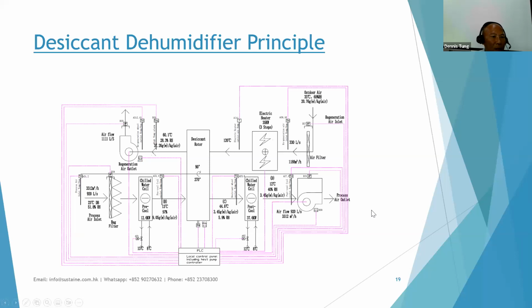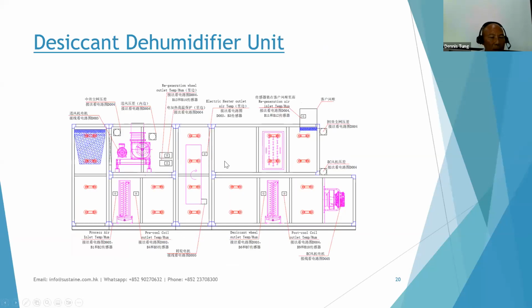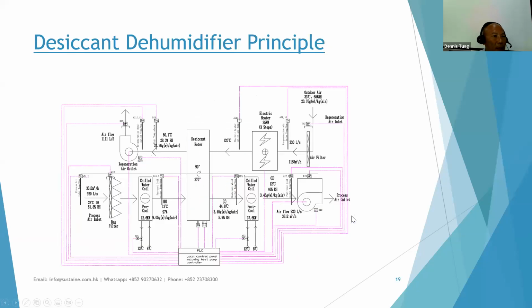Later on, I would like to introduce the heat pump, which nowadays can achieve a very high temperature. I would like to demonstrate a unit that looks like this, a very big unit. All right. For example, in place of this electrical heating element, heat pumps nowadays can provide an outlet air temperature of 120 degrees Celsius. So by using a heat pump to provide the heat energy to this regeneration process, the energy consumption of this desiccant dehumidifier will be much lower than before. And this could be an option we can evaluate in our HVAC system to see which method provides the best overall energy effectiveness for our building.